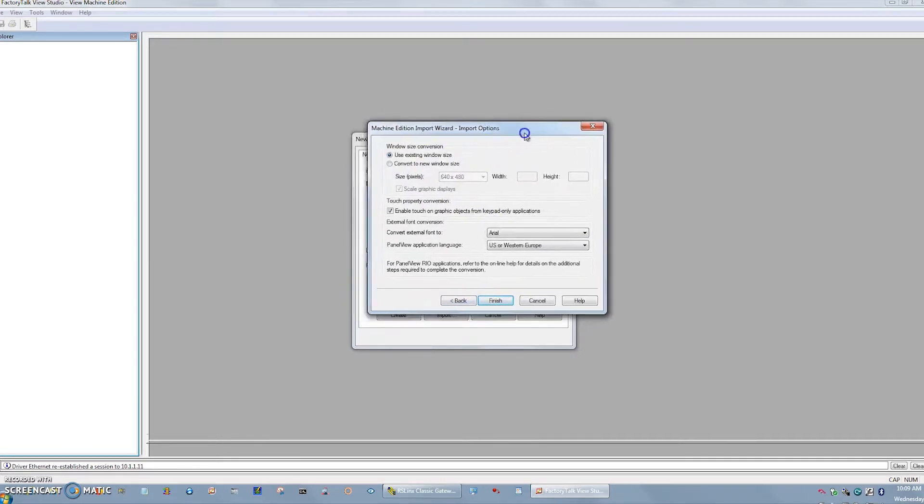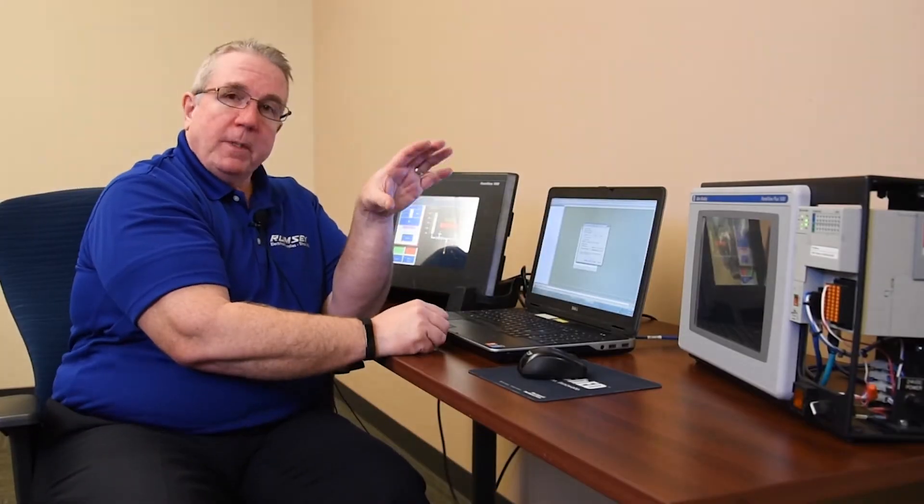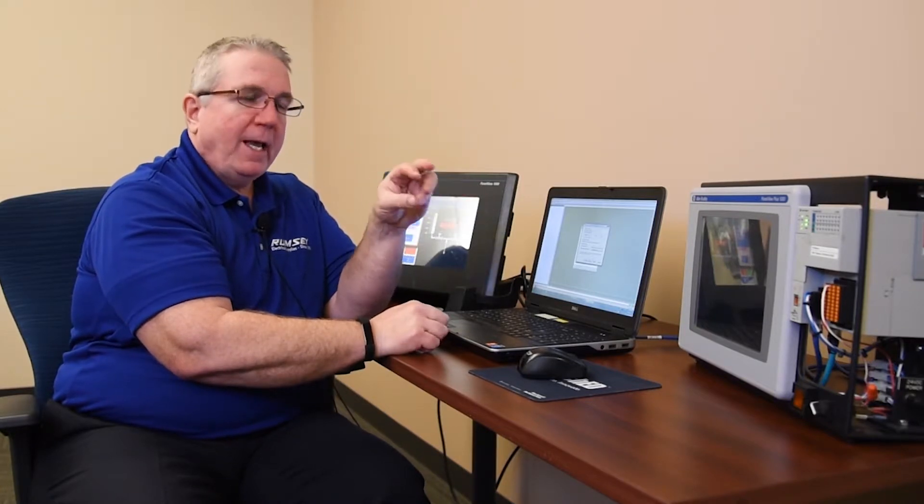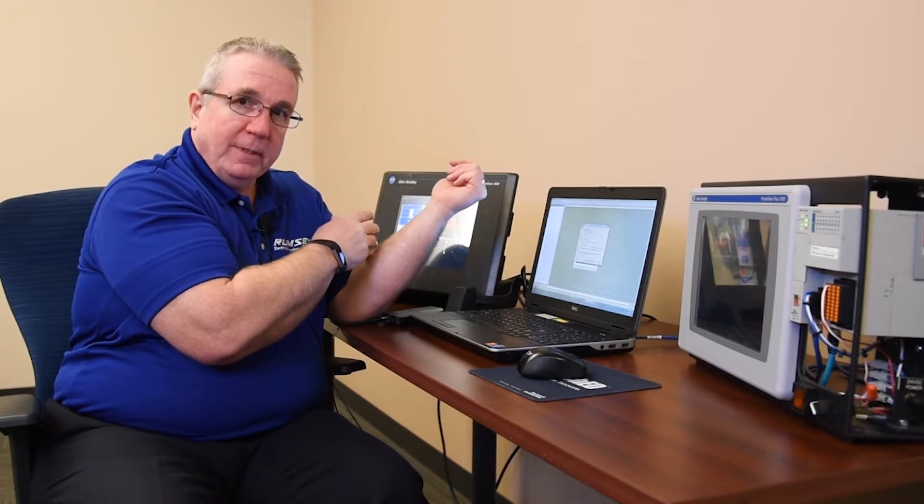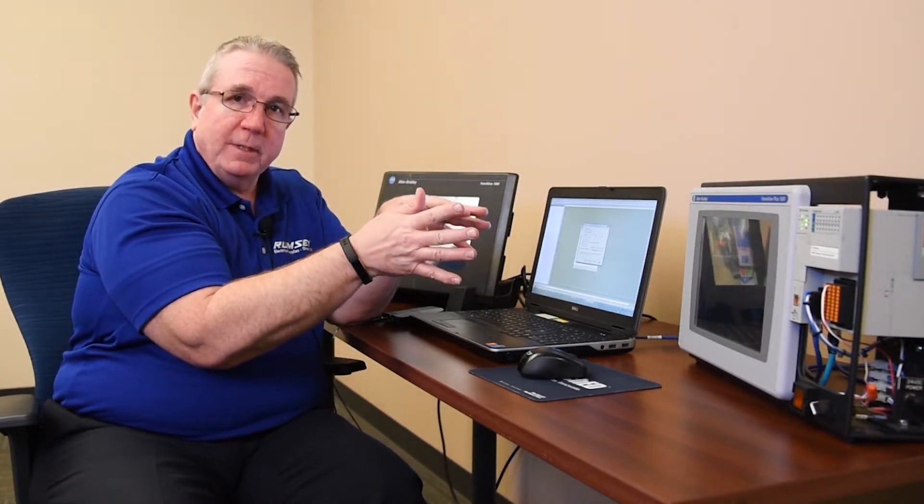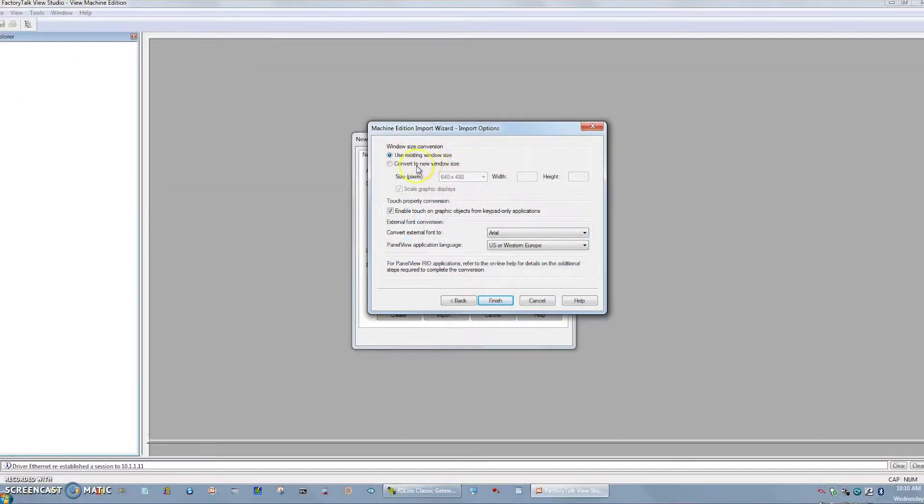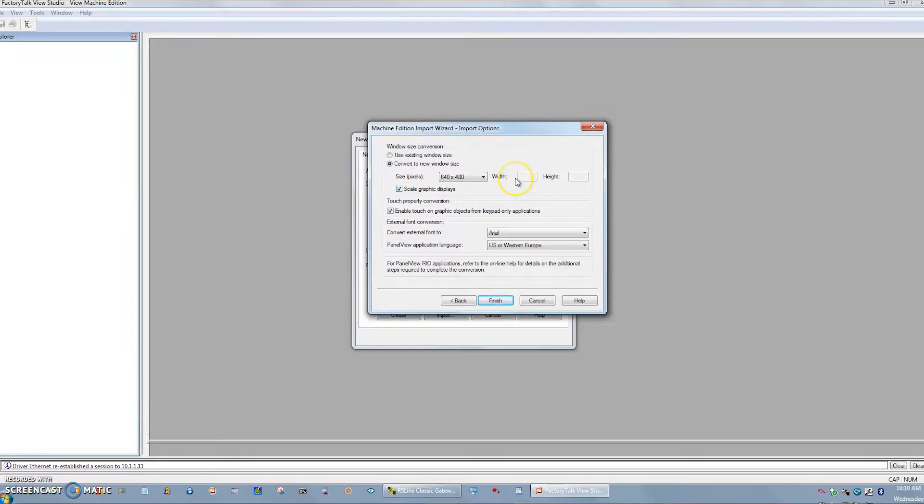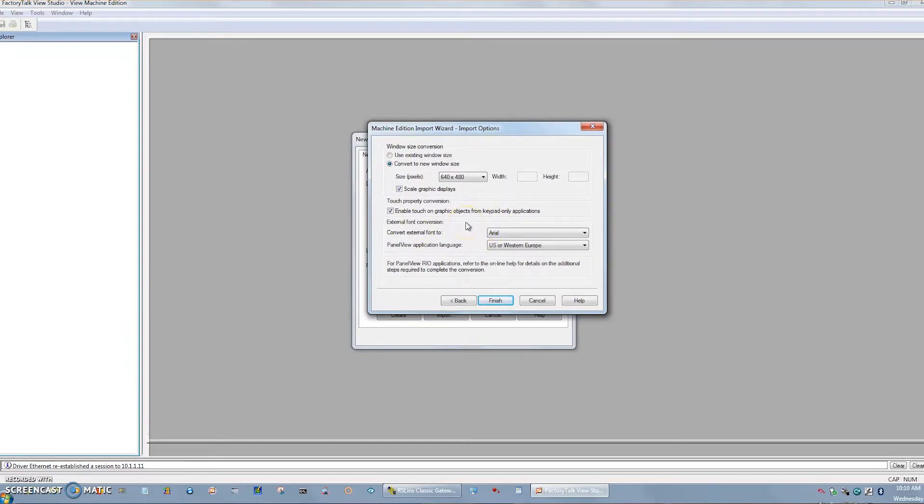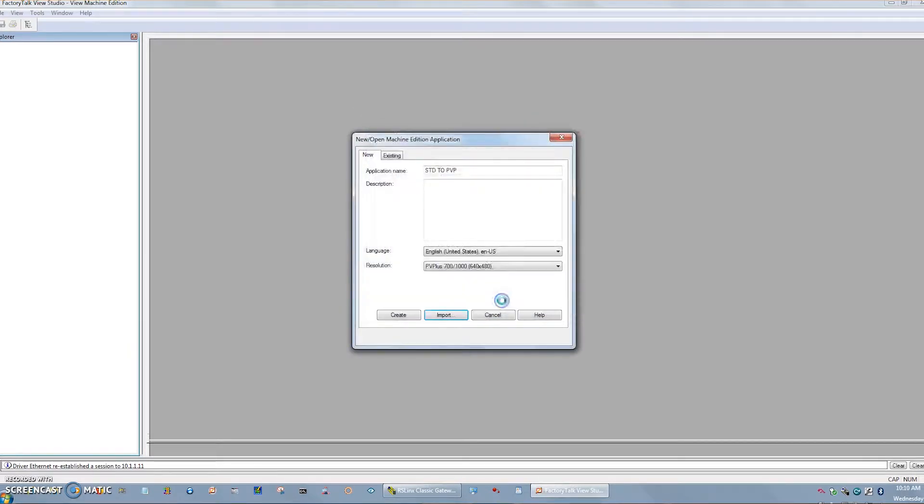Now it's saying convert the window size. Now a PanelView Plus and even some of the PanelView Plus 7s have a particular resolution you have to match it for. This 1000 is very close to a PanelView Plus 1000 for as far as sizing of the screens. So it would be a 640 by 480 size. If you notice it says scale graphics, it's going to do its best to scale all these graphics to make it look the same as it was from the original on the new product. Enable touch. That's important. You probably want to still use the touch feature. And really, just go onwards and hit finish and hesitate for a minute. So now it's generating all the files.